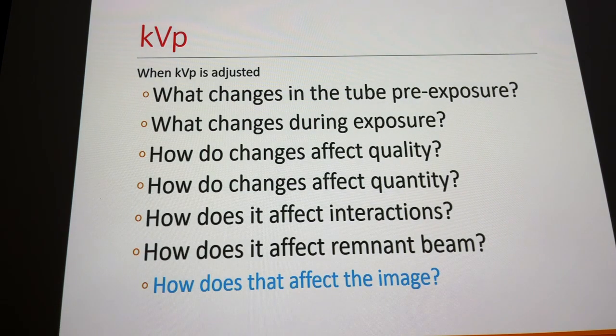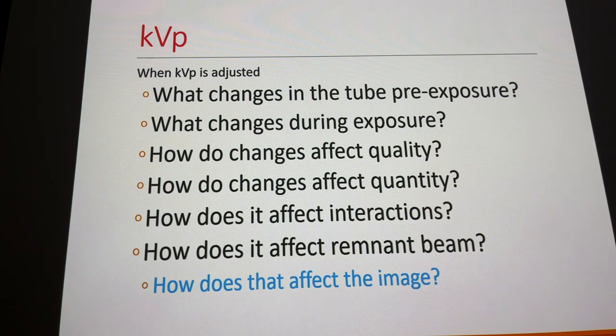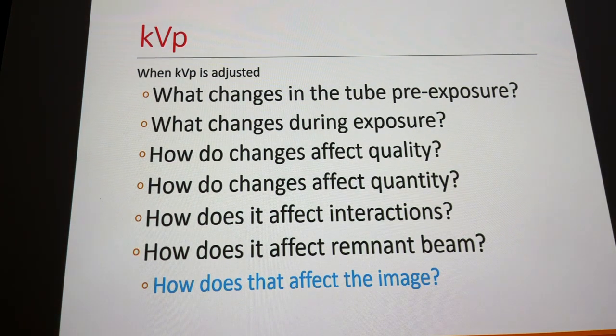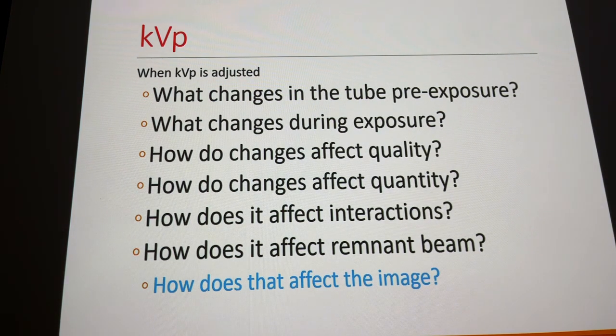Pre-exposure, there's not a lot of voltage inside the X-ray tube until you depress the exposure button. At that point, the potential difference between cathode and anode increases, accelerating electrons across the tube — the higher the KVP, the faster they move. When they hit the anode, we get interactions: we create X-rays through bremsstrahlung, some characteristic X-rays if KVP is high enough, but mainly heat and a small amount of X-rays.